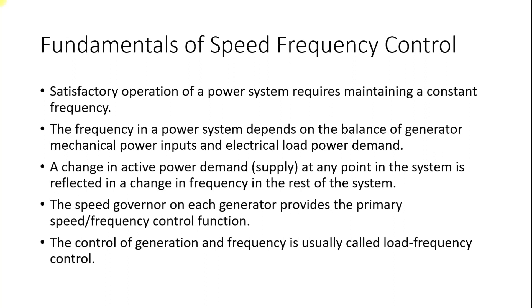The satisfactory operation of the power system requires maintaining a constant frequency. The frequency in a power system depends on the balance of generator mechanical input and electrical load power demand. P electrical should be equal to P mechanical — in other words, at a system level, electrical demand should be equal to the power generated. As long as demand equals generated power, the system frequency remains at its nominal value. For a 60 Hz system the nominal frequency will be 60 Hz; for a 50 Hz system it will be 50 Hz. If generation increases beyond demand, frequency will increase; when demand becomes greater than generation, system frequency will decrease.